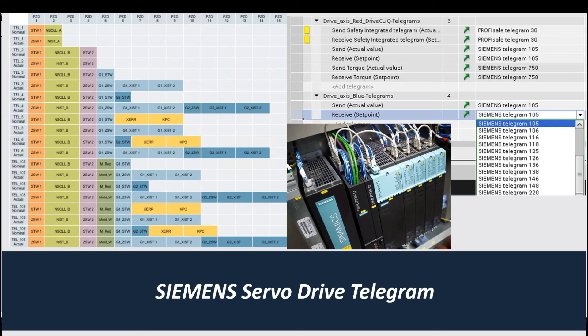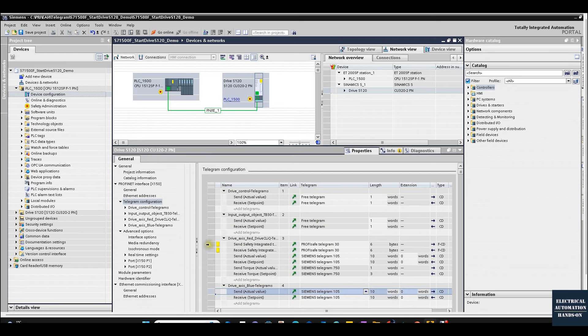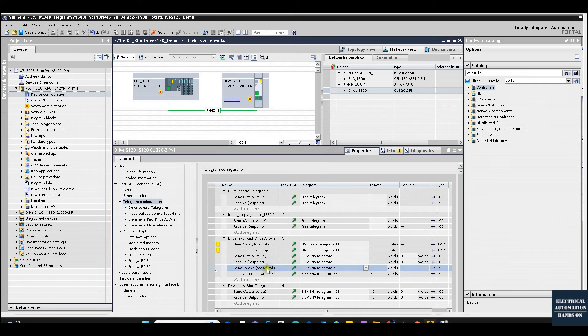In this video I'd like to discuss Siemens telegrams. When you are using Siemens TIA Portal software with the S7-1500 PLC or S7-1200 PLC and set up communication with a drive system — either VFD or servo drive — you have to set up the Siemens telegram. Typically from the drive side you will see the safety telegram 30 and the drive positioning control telegram 105 and the torque reduction telegram 750. This is the typical telegram group used with middle and high-end servo drives, for example Siemens SINAMICS S120, S210, or the newly released S200.